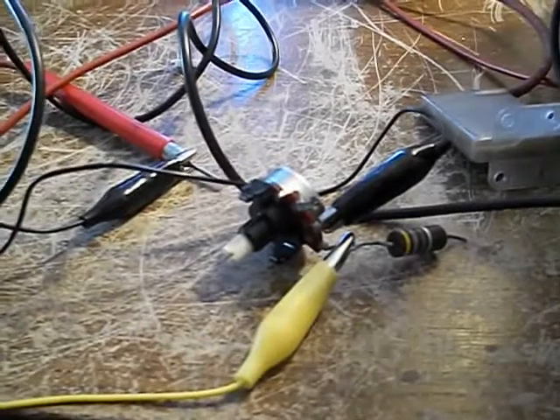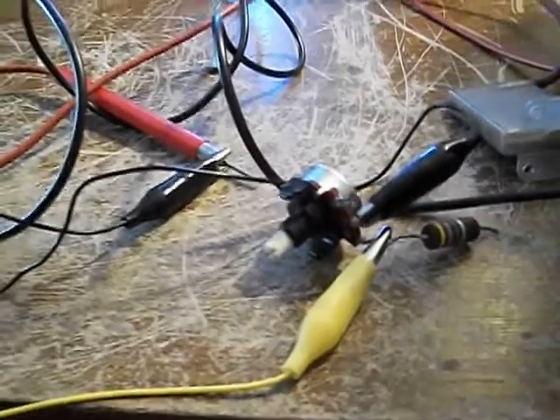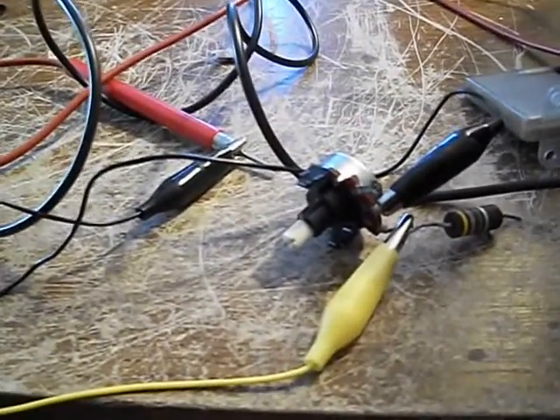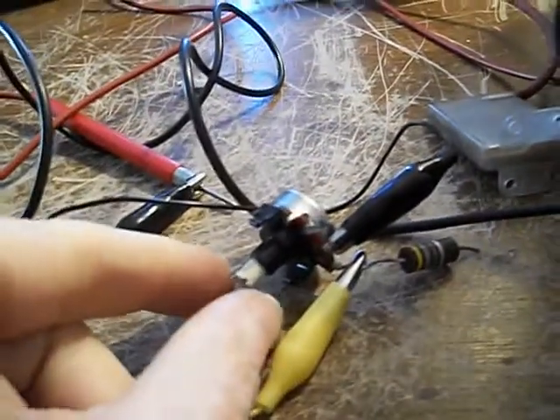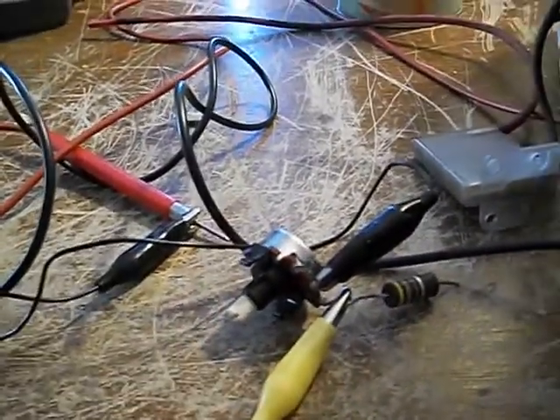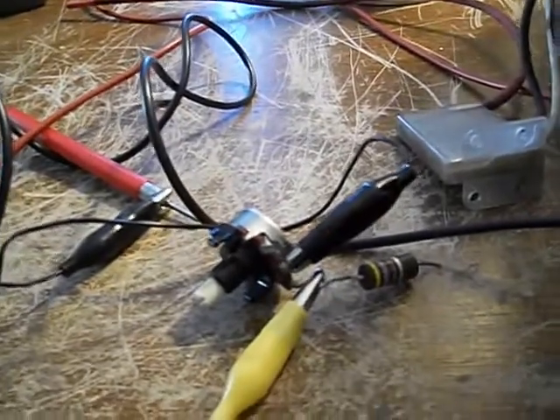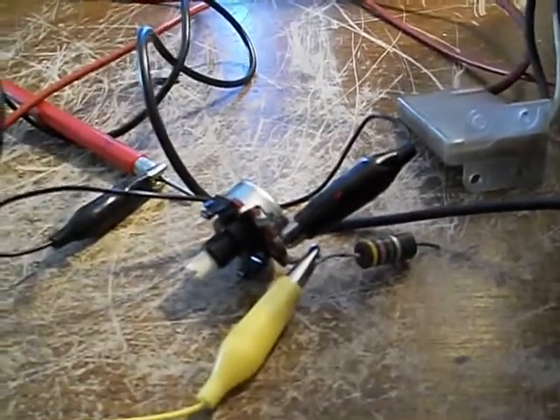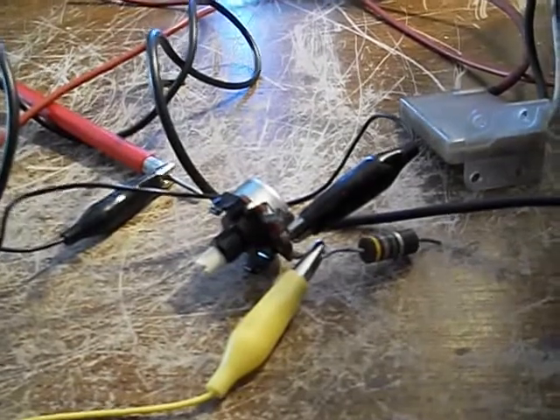In this particular case, it was the extreme end where the focus voltage setting was at the lowest. That would be fully counterclockwise here. Now, I checked the voltage with a high voltage probe to see which way it was going, just to confirm that.